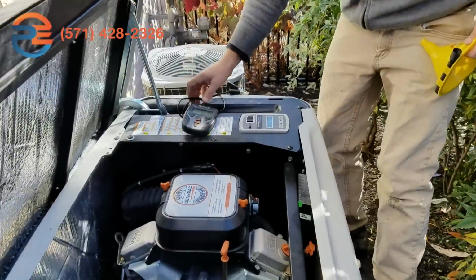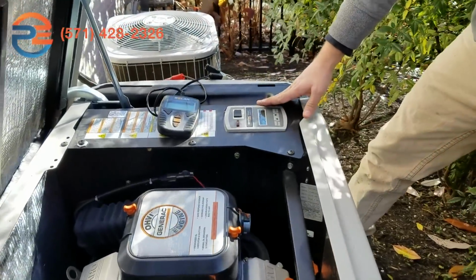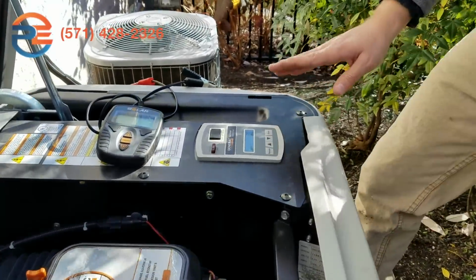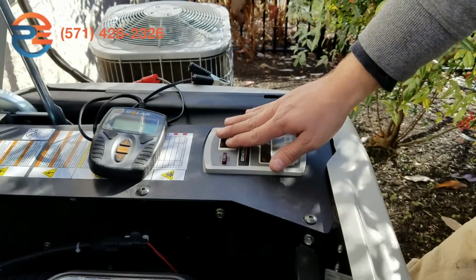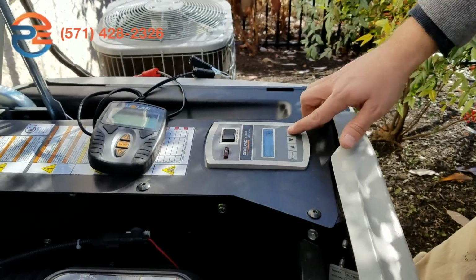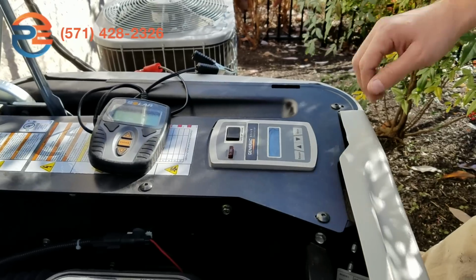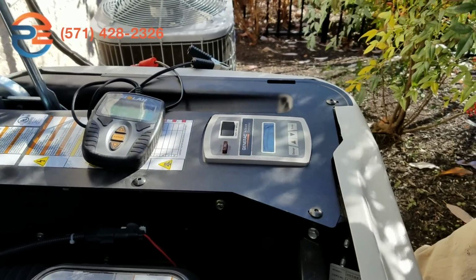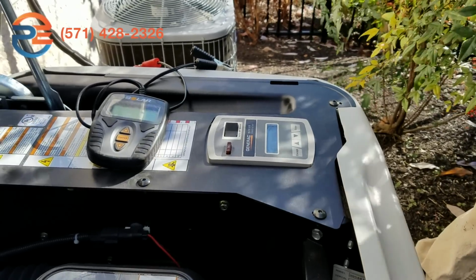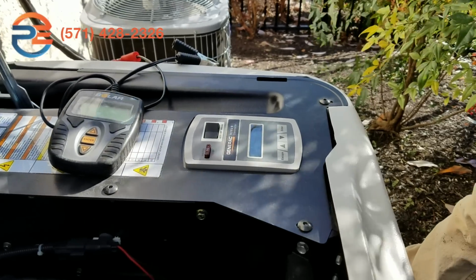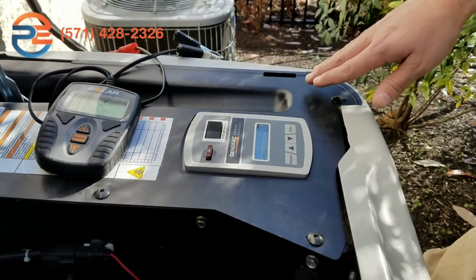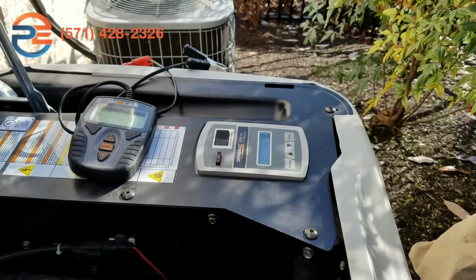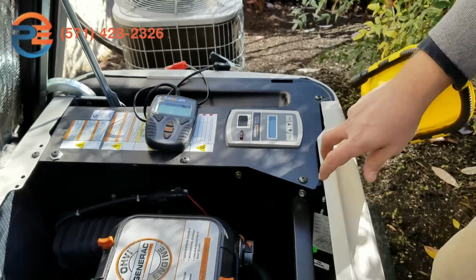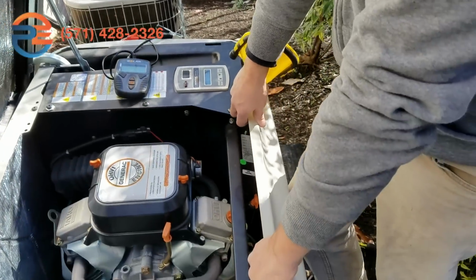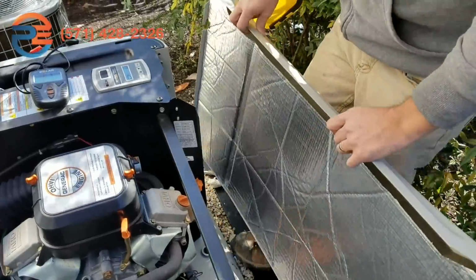We want to first go to our control panel to see if we have any errors or warnings. If we do, we're going to want to clear them by turning the generator to off and hitting enter twice. Then turn the generator back to auto and see if the error returns. We're clear, everything looks good, so we can now inspect the generator. To do that, we're going to lift the hood, simply lift up and pull out to remove the front cover.